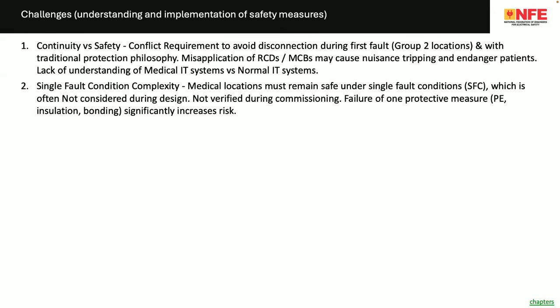Single fault condition complexity. Most of the biomedical equipment are capable of working in normal condition, of course, and they are also capable of working during single fault condition. Single fault condition means there is a fault, everybody knows the fault, and the equipment are capable of creating a safe environment, which is an inbuilt feature inside each of the biomedical equipment. This means the biomedical equipment are made with extreme care so that even if there is a fault, the safety is not compromised.